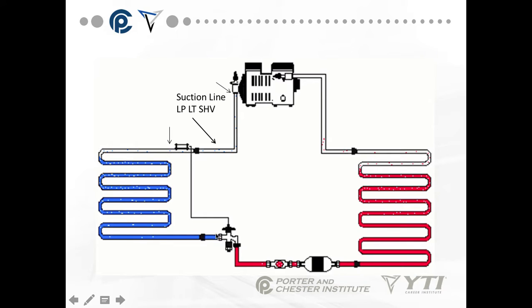The refrigerant then sprays into the evaporator, boils off, is superheated, and comes into the suction line as it leaves the evaporator. It is a low-pressure, low-temperature, superheated vapor where it moves into the inlet of the compressor. Our entire cycle includes the discharge line, the condenser, the liquid line with optional filter dryer and sight glass, the metering device, and the evaporator.